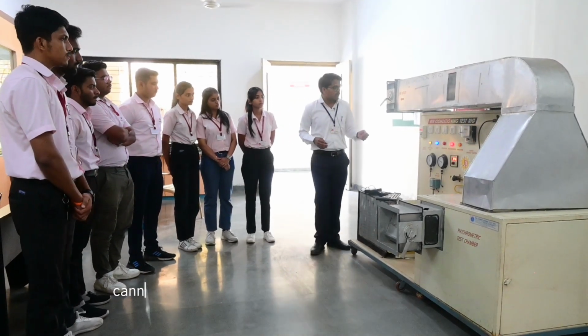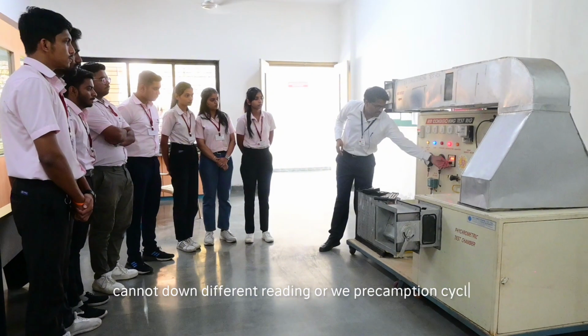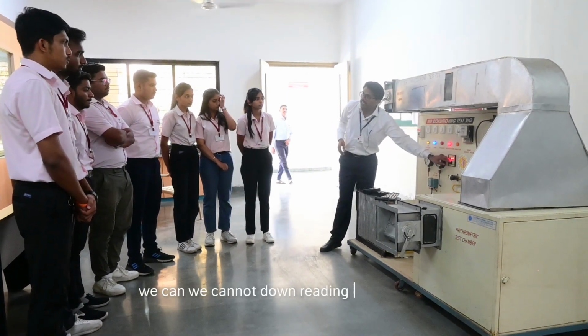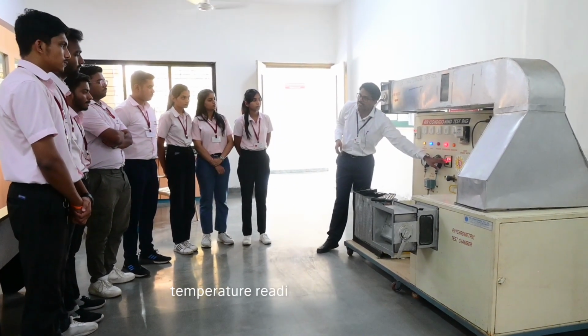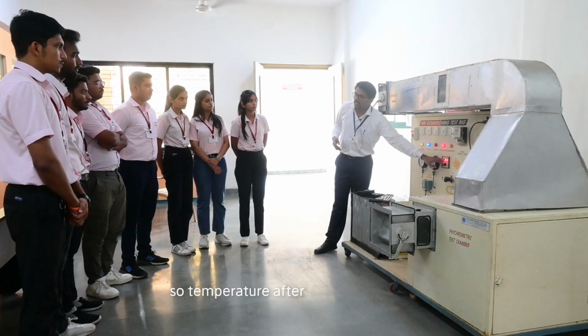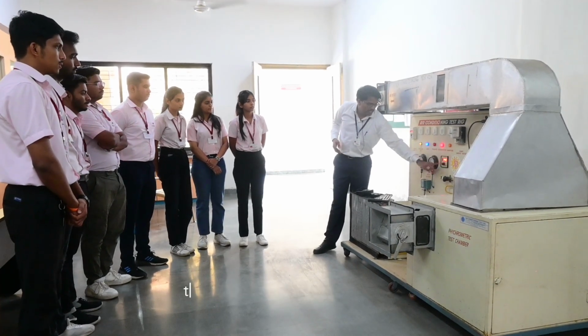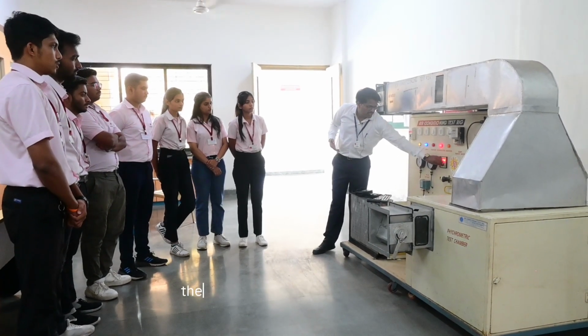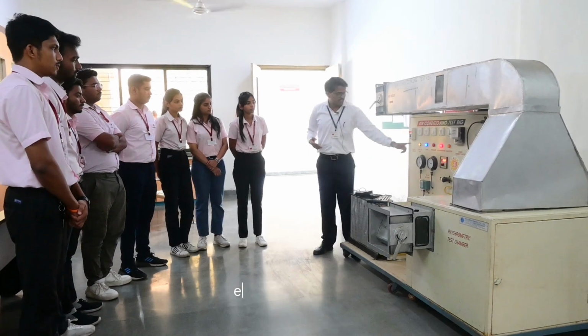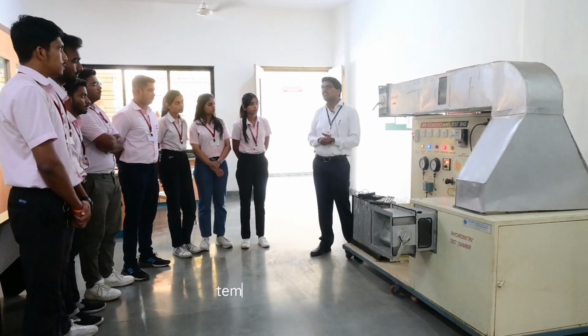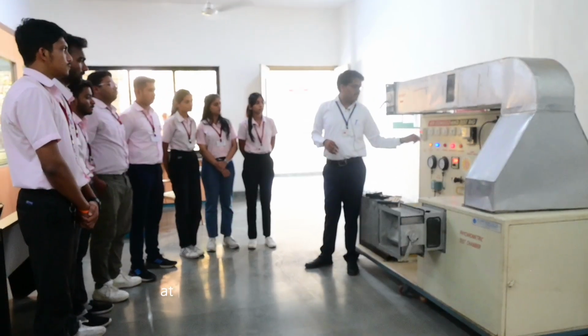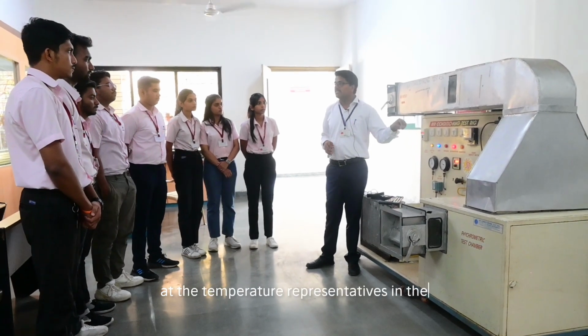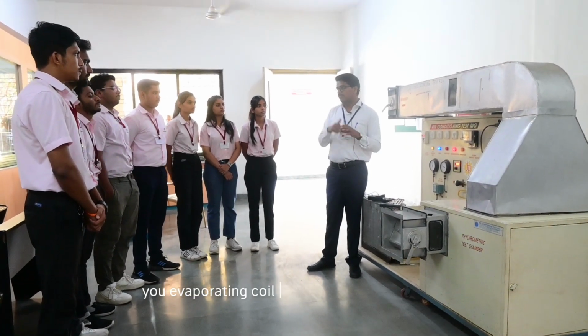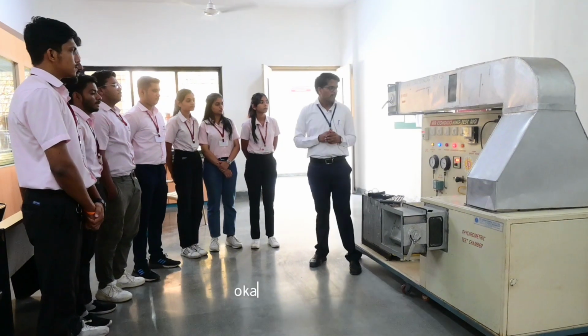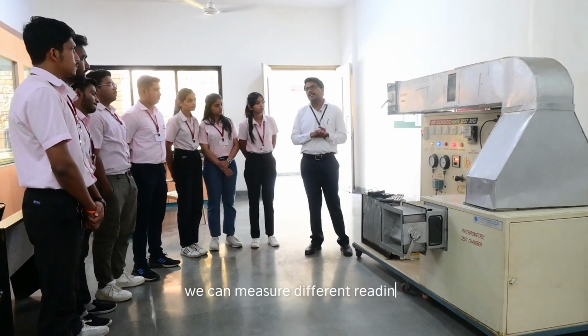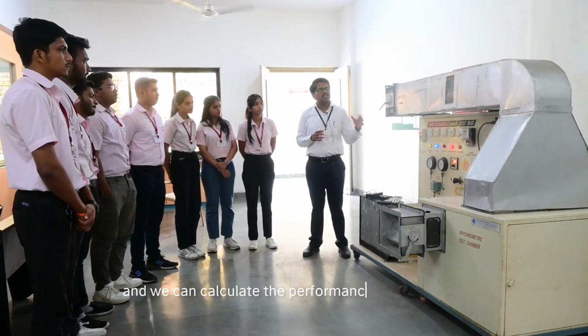Okay. So we can note down different readings for the vapor compression cycle. We can note down the temperature readings in degrees Celsius. So temperature after compressor. Okay. Then temperature after condenser. Then temperature after expansion device. So we can see after the expansion device the temperature is lower. Okay. At that temperature, the refrigerant is in the evaporating coil and it will absorb the heat. So in this way we can measure different readings and we can calculate the performance of this test rig.